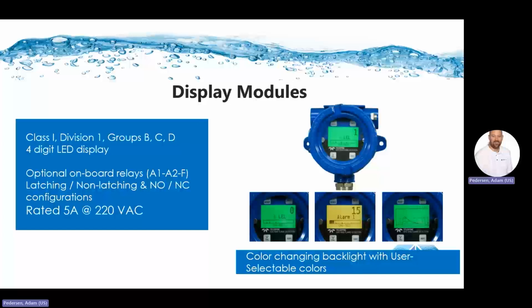Housed in a rugged, weatherproof, explosion-proof aluminum or stainless steel housing, this display module can be mounted directly to the gas detector, or it can be mounted remotely. All module functions can be operated in a hazardous area using a magnetic wand to access the non-intrusive controls. And this display can be used in our Class 1 Div 1 or Class 1 Div 2 detector.